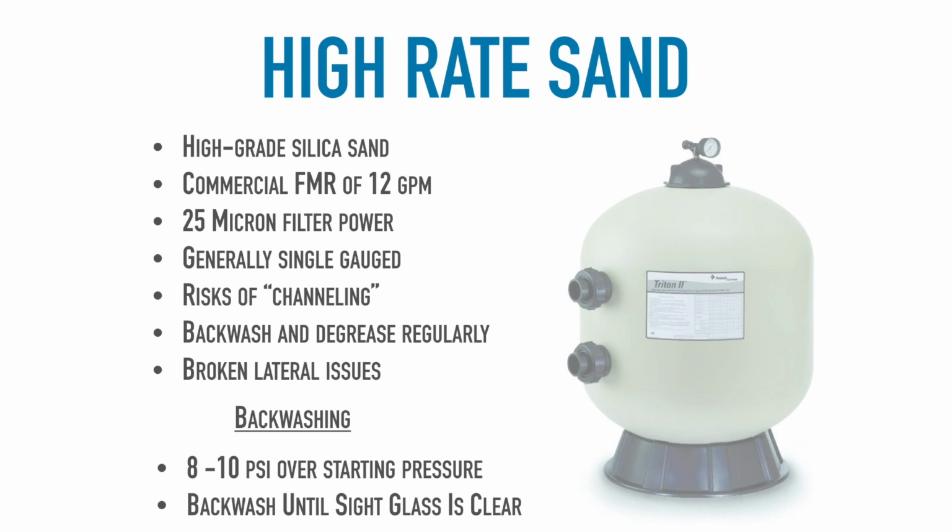Now, this gauge is going to essentially show us the health or the life of our filters themselves. Over time, our filters are going to start compacting with a bunch of gross stuff. And as a result, it's going to start to raise that filter pressure. As that filter pressure raises, the sand filter itself starts to clean a lot less. Now, what we're looking at is we want to see a raise of 8 to 10 psi over start.